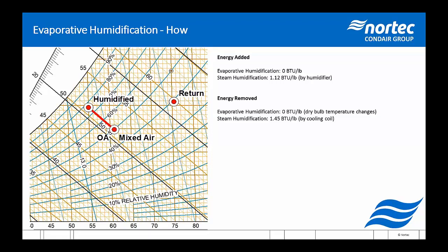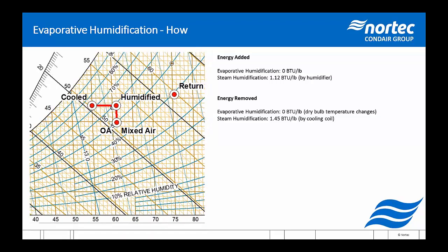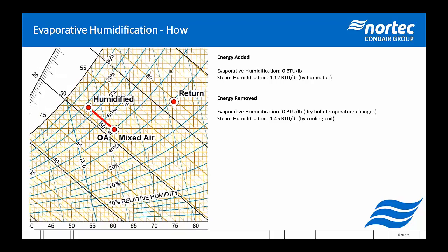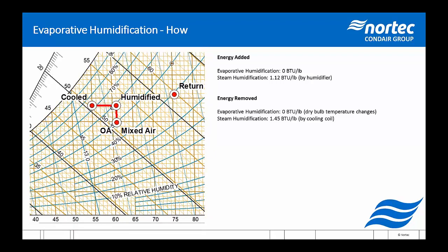So in this case, if we go back and forth here, we're using 100% outside air because our air side economizer is in full bore. We have to humidify it and we have to cool it. From the humidified by evaporation standpoint, we are putting in effectively zero energy. We are just using the evaporative humidifier to cool the air. We can look at some other situations here as well.